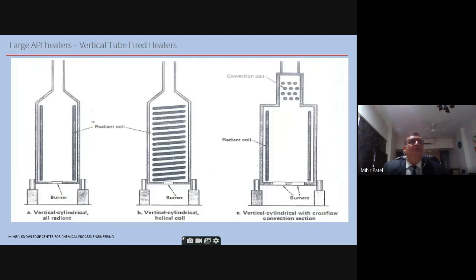Now there are different types of fired heaters. One, on the left, is the all radiant type. This is of very low efficiency. There is no heat recovery. Efficiency is maybe 60%. Only the radiant section is there. These are for small services. In the middle, you see the vertical cylindrical helical coil. Now there are two types of fired heaters: vertical and cabin type. We'll discuss both. We are talking about the vertical type now. And on the right, you see the vertical cylindrical. Each has its own capacity limitation, so different pros and cons are there for each.